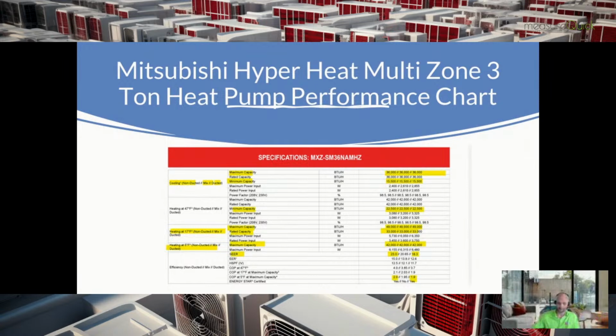And then you see it's the same deal with the efficiency. Look at the difference in efficiency depending on what combinations you're using. It is quite significant, and it does come into play depending on what you're using these things for, especially in the program world, when you're trying to install certain equipment to meet modeling requirements and certain efficiencies to meet the model. You really have to pay attention to what you're getting out of this, because look at this. If everything's non-ducted, you're getting 23 SEER out of these. They're rated at 23 SEER. If everything's ducted, you're only getting 18 SEER. That's a significant difference. If you've got a mixture, what just happened?